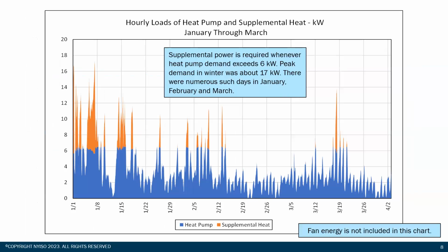Now, those 400 hours are not concentrated only in a couple days of the year. This chart is derived from the hourly output of the DOE model, which is the same basis as ResStock. They essentially use the same approach. You can see that the heat pump is clipped or capped, its maximum output is about 6 kilowatts thermal to heat the home.